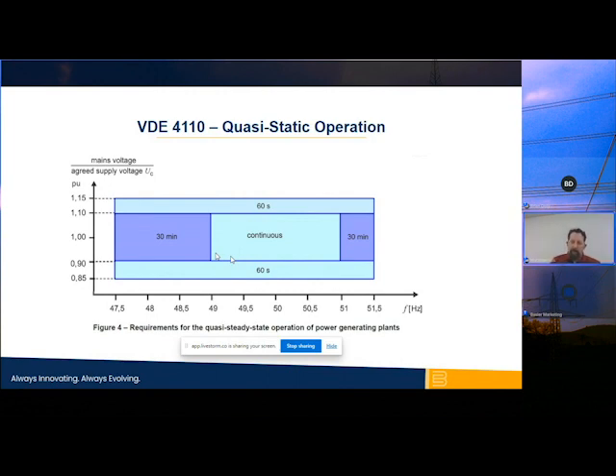Likewise, I'm going to have the same scenario where I'm monitoring the grid, but now I've already disconnected. Once I get above those preset thresholds, with the same type of guidelines based upon the grid code, the grid has stabilized to a condition where I need to synchronize. So it'll tell us when we need to come in and reconnect. The grid code defines where this machine has to stay online and operate. And again, these will vary from place to place and application to application.